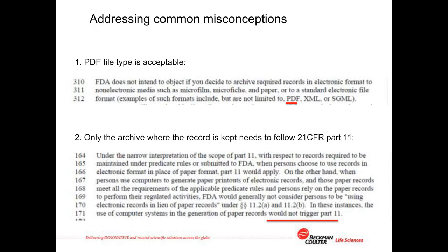In their 2003 guidance, the FDA sought to make it clear that the 21 CFR Part 11 rule was not written to try to prevent criminal activity. It was written to avoid manufacturers accidentally losing or not being able to read electronic records retrospectively. Many interpret the rule as enforcing encrypted file formats or formats that cannot be deliberately edited. This is not the intention. Just as with paper records, the intention is that the records should be kept safe and secure so that they can be retrieved when required in the future. Again, just as with paper records, it's not the format of the record that the FDA is concerned about. It is the way they are stored to prevent accidental corruption of the information contained in the record or loss of the record itself.